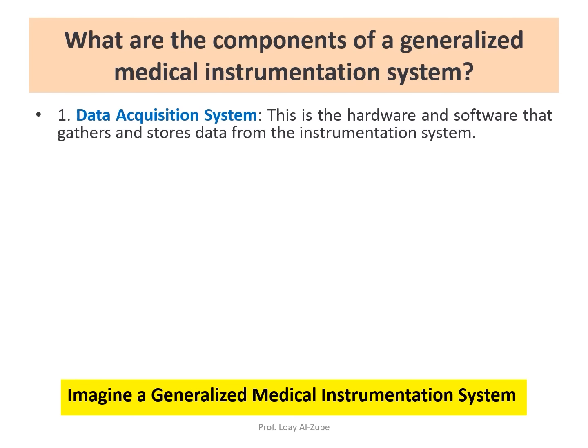Remember when we did the experiment with the iWorks, the EMG, that we collected with the dumbbells, right? So that is a data acquisition system, and that is our job, to design, and to calibrate, and to do preventive maintenance. So if someone hires you in a hospital, they will expect from you, we don't want you to do maintenance for the device's electrical components, but we would like to make sure that you as a biomedical engineer know how it works and know how to operate it, and then do calibration and preventive maintenance.